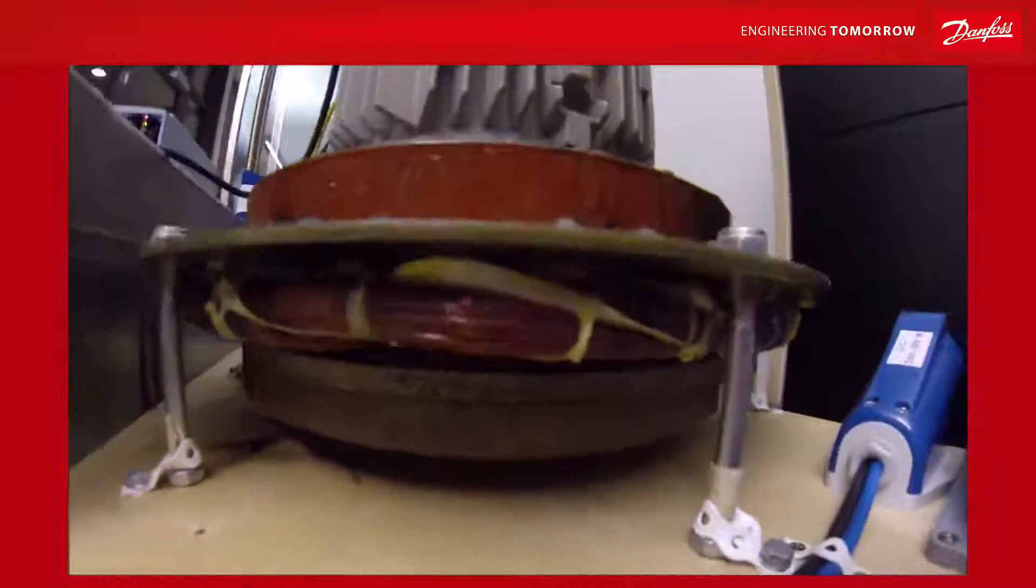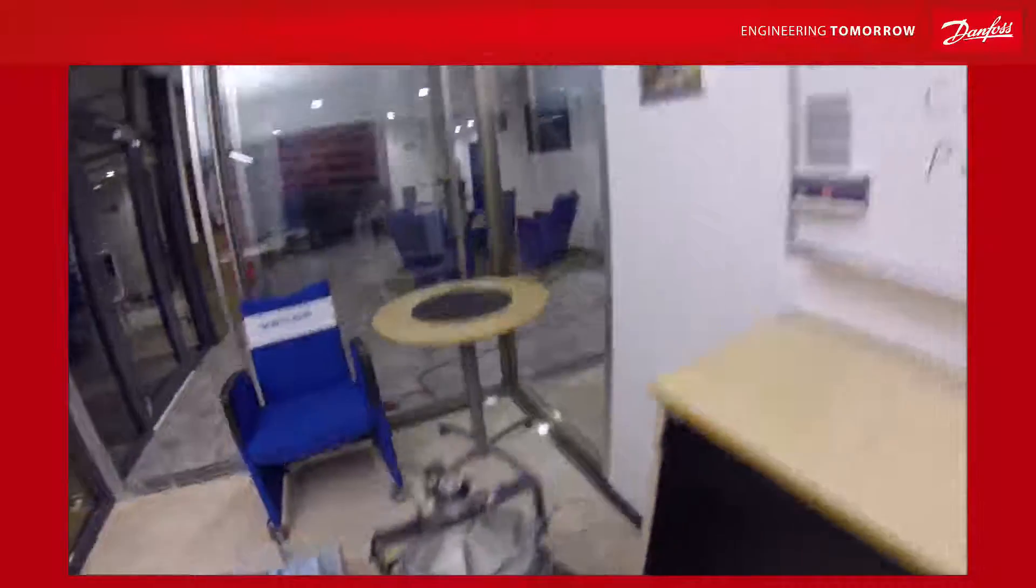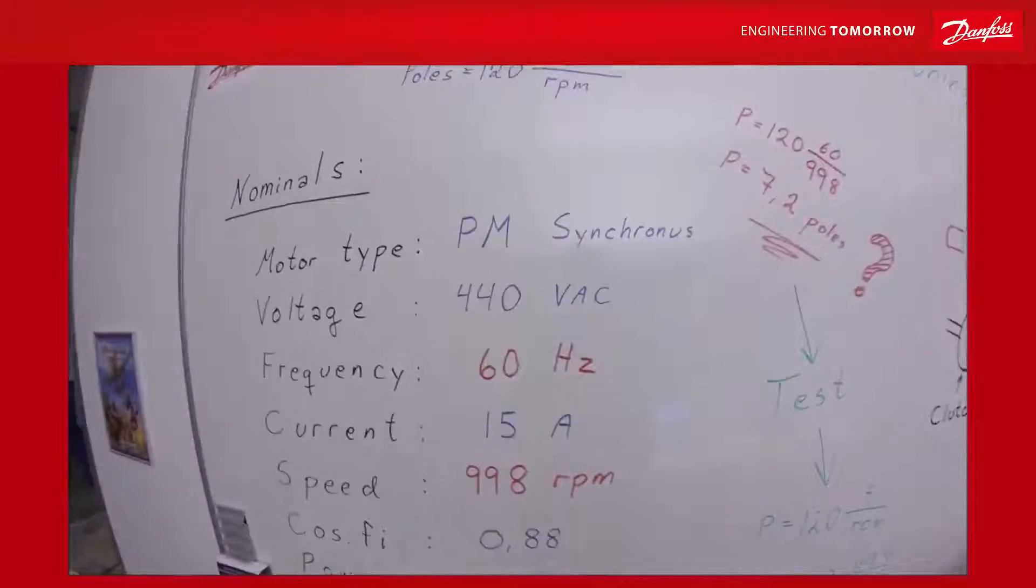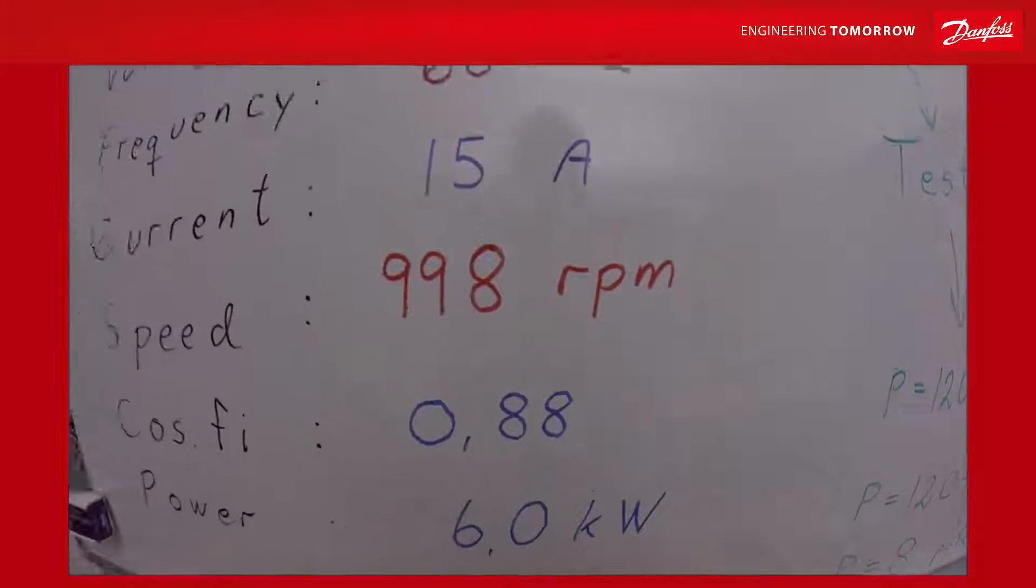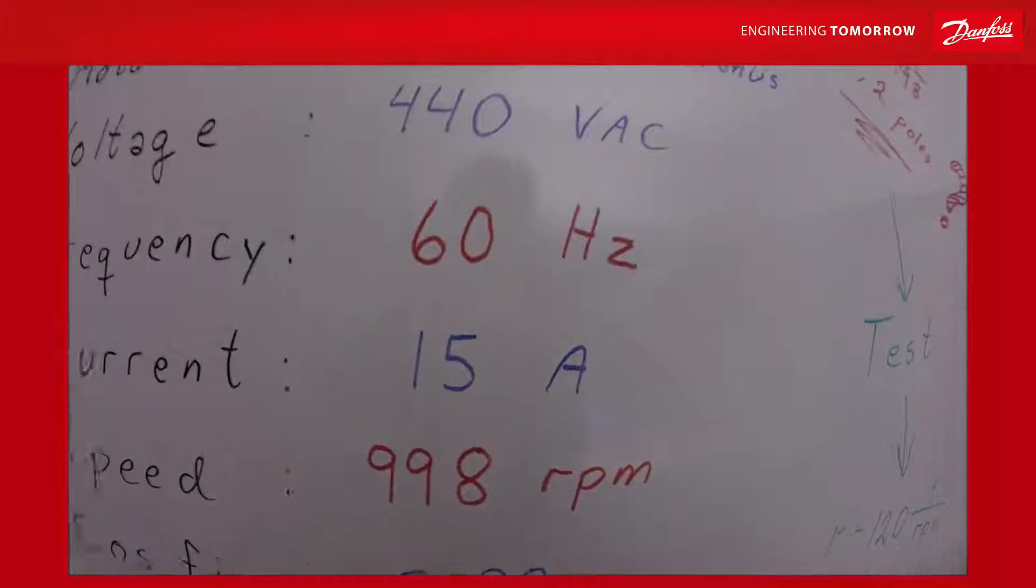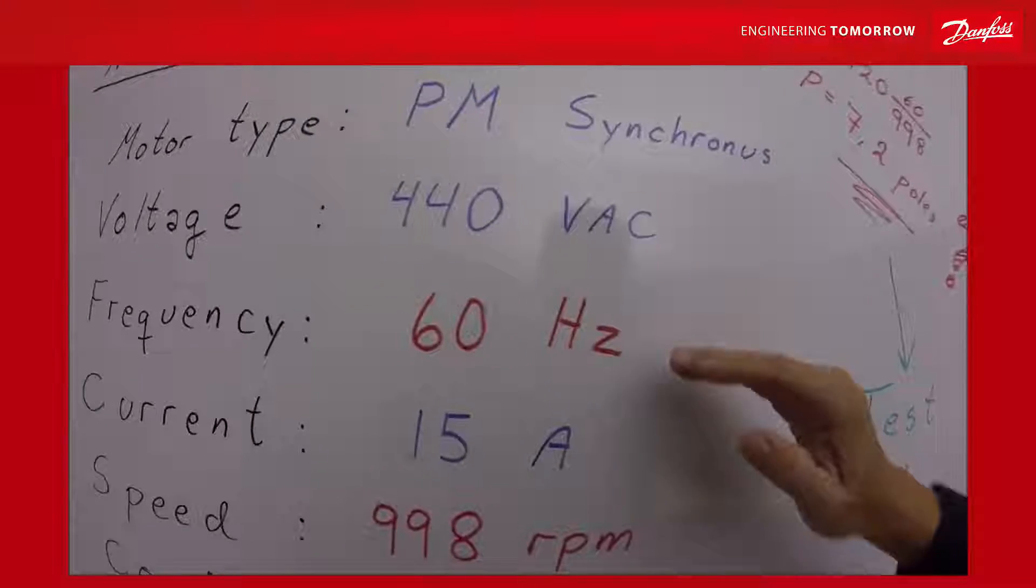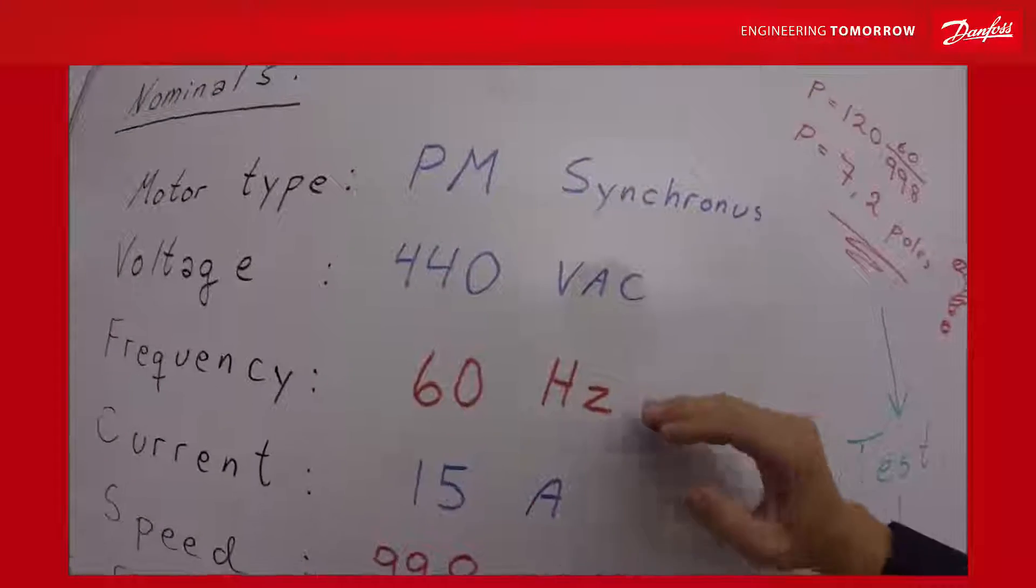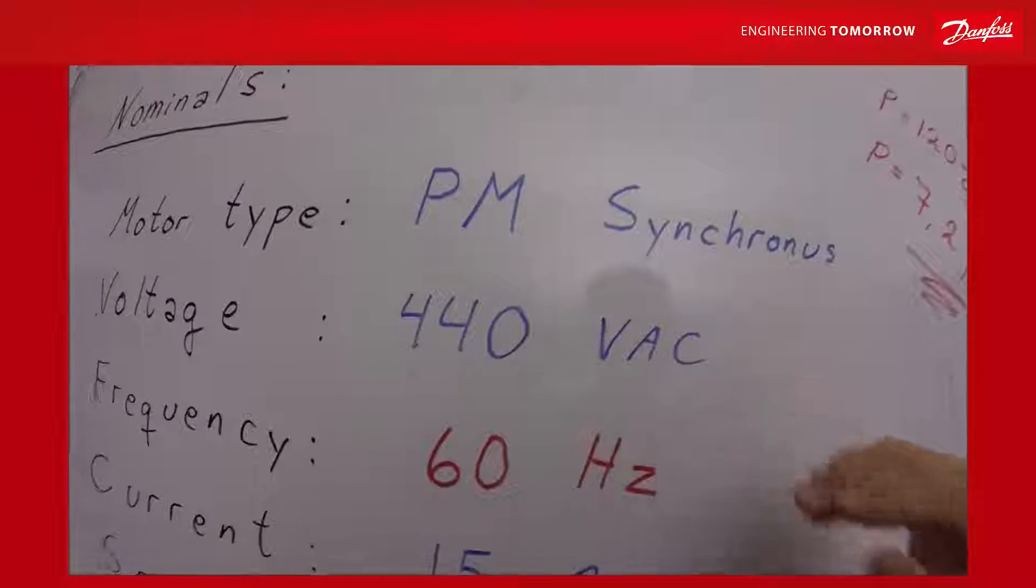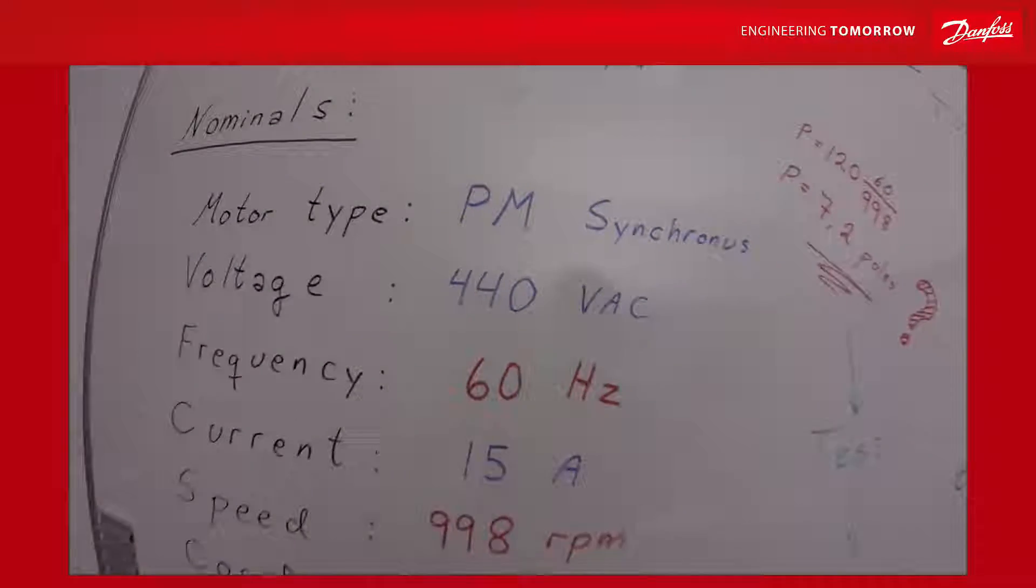To achieve correct tuning we need to know the motor nominal data. The motor vendor has given me this data. Are they right? Are they precise enough? Especially the relation between the frequency and RPM is important and also the relation between the frequency and the voltage which is the back EMF curve. Let's check.